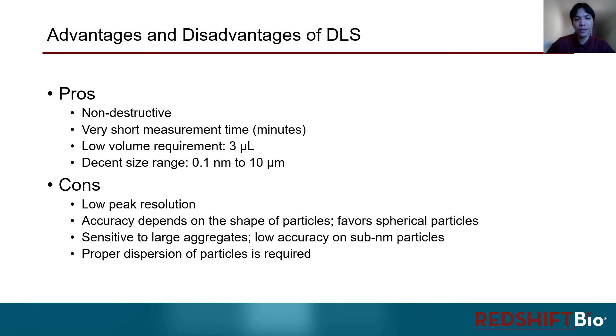Like other techniques, DLS has both its advantages and limitations. Here are some of the highlights. DLS is a non-destructive technique, meaning that the samples measured can be recovered for future use. Each DLS measurement is usually within only a few minutes, so very fast measurements. The volume required can be as low as 3 µL. And also, DLS covers a very good size range, from 0.1 nanometer to 10 microns.